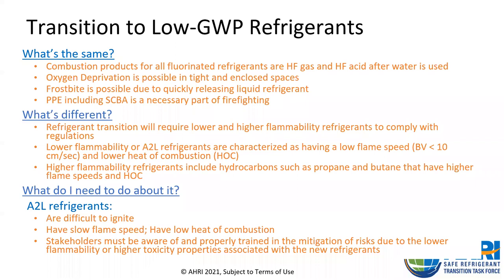Well, particularly as we're concentrating on the A2L refrigerants today, we need to recognize and note that A2L refrigerants are difficult to ignite, have a low, slow flame speed, have a low heat of combustion, and stakeholders must be aware of and properly trained in mitigation of the risks due to lower flammability and properties associated with the new refrigerants. And we're gonna go and look at some of those. So now let's look at these refrigerants.